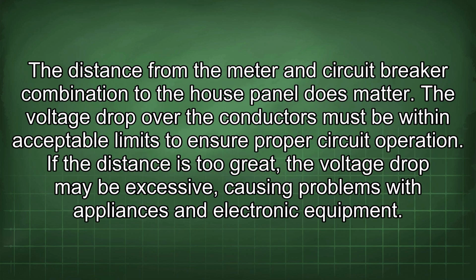The distance from the meter and circuit breaker combination to the house panel does matter. The voltage drop over the conductors must be within acceptable limits to ensure proper circuit operation. If the distance is too great, the voltage drop may be excessive, causing problems with appliances and electronic equipment.